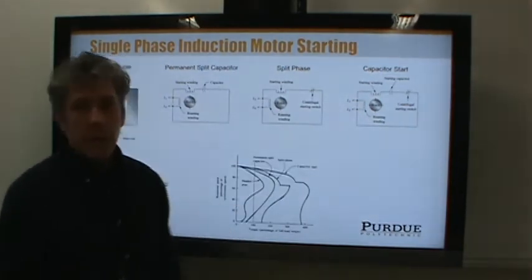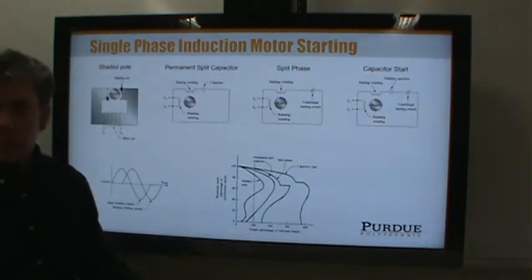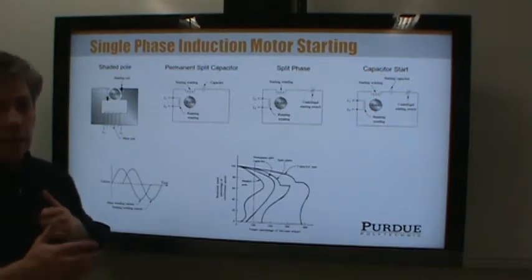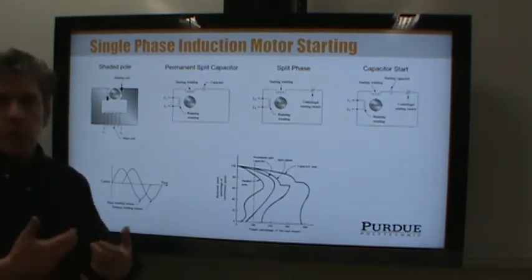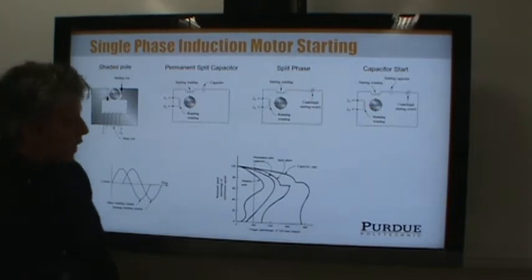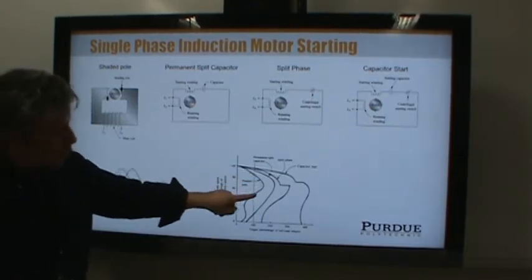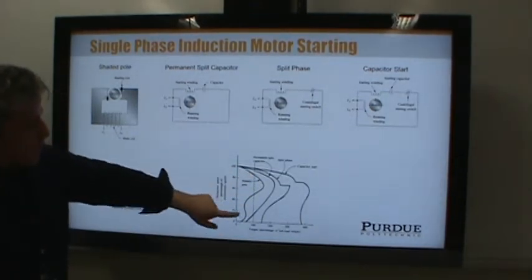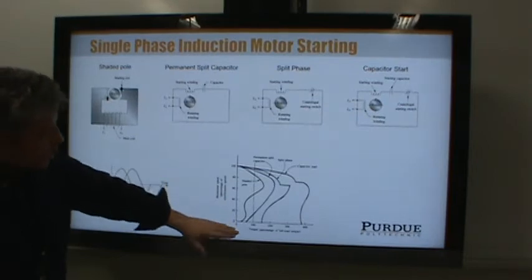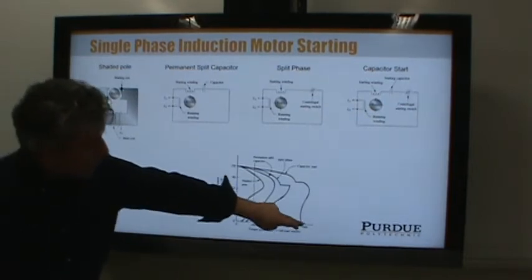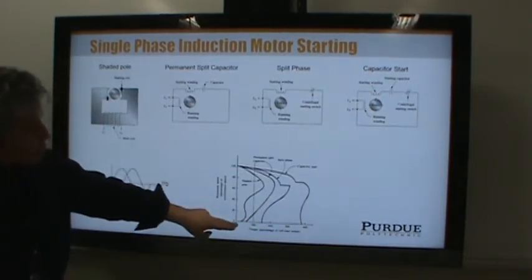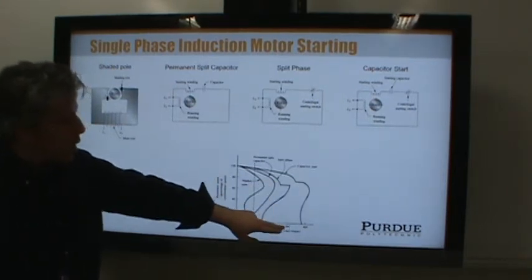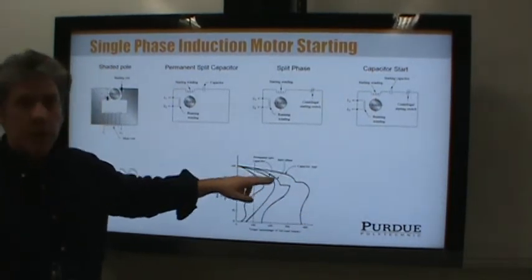Disconnecting the start winding allows the motor to run at higher efficiency. This is just a mechanical and electrical mechanism to get the motor to start turning, then let it continue at higher efficiency. You'll notice the shaded pole motor curve is pretty poor — relatively low torque versus speed — whereas the capacitor start is ideal for a compressor.